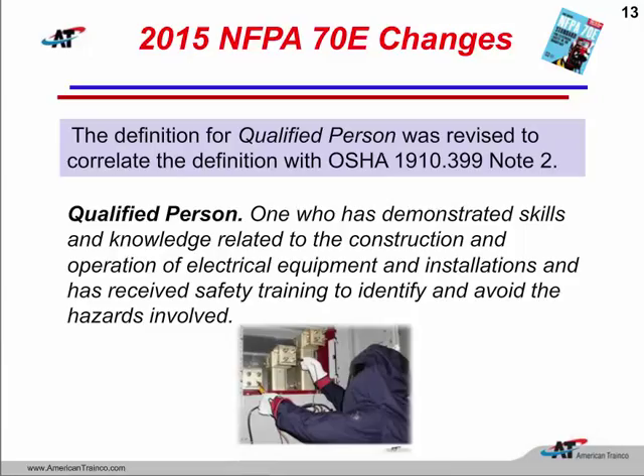Well, the previous definition did not have that word demonstrated in there, so to be a qualified person, not only are you just going to talk the talk, but you've got to actually demonstrate that you can perform that work safely and that you do have an understanding of the equipment that you're working on, how it was made, how you have to operate it, how it was installed, and that you have received safety training, documented safety training, so that you can identify any hazards associated with that equipment and that there is a procedure in place to avoid those hazards. So this definition will go through all of the NFPA standards.